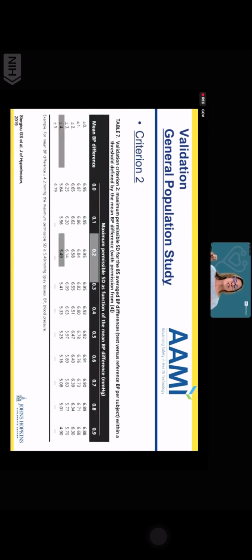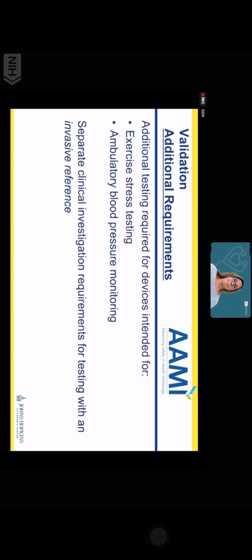Then for criterion 2, you take 85 average blood pressure differences, and then you determine what that average difference is. And then on the table I'll show you on the next slide, you're able to determine what the allowable standard deviation is, and that will allow you to know whether or not your device can pass. In this example, when they were doing that criterion 2, you can advance one more time. They came up with a mean blood pressure difference of 4.2 millimeters of mercury, which then allowed them to have no more than 5.49 millimeters of mercury standard deviation, and so that would be used to interpret what the results were. If you could advance twice, please.